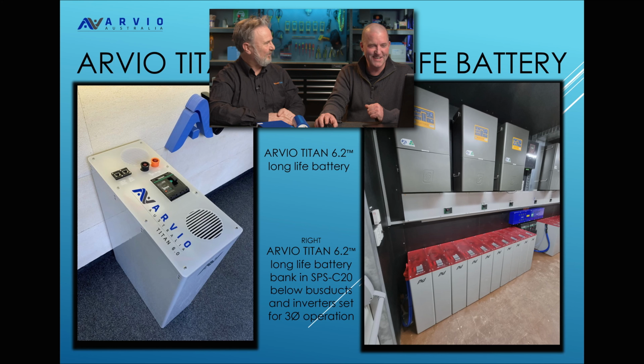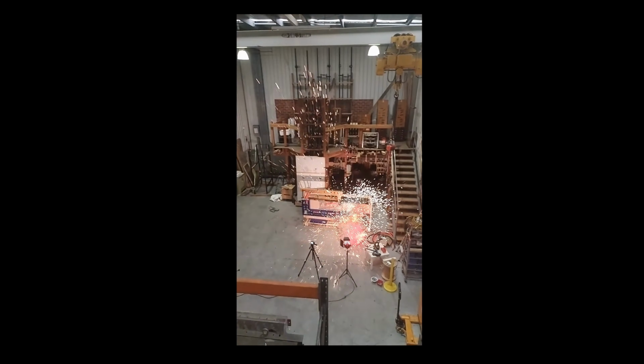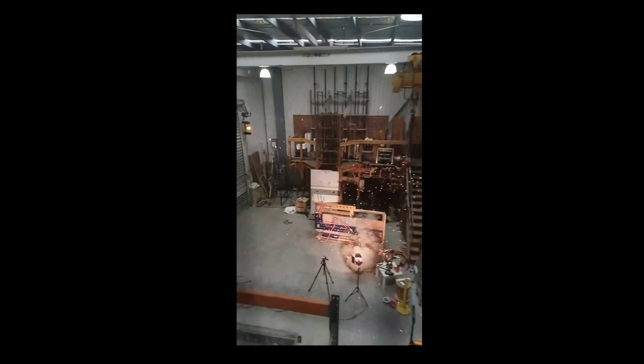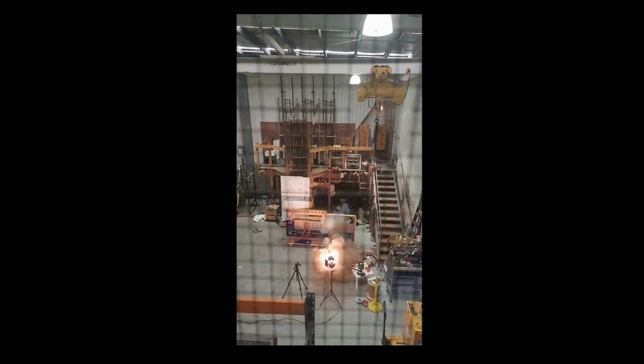Yes, it was rather loud from memory. I can play that back to you at some point. We short circuit tested it at 50,000 amps at 800 volts to see what would happen if you shorted out the connectors, and they naturally exploded. But then we tried it with the fusing, and the fuses just failed perfectly. So we proved what would happen if you didn't do it properly.